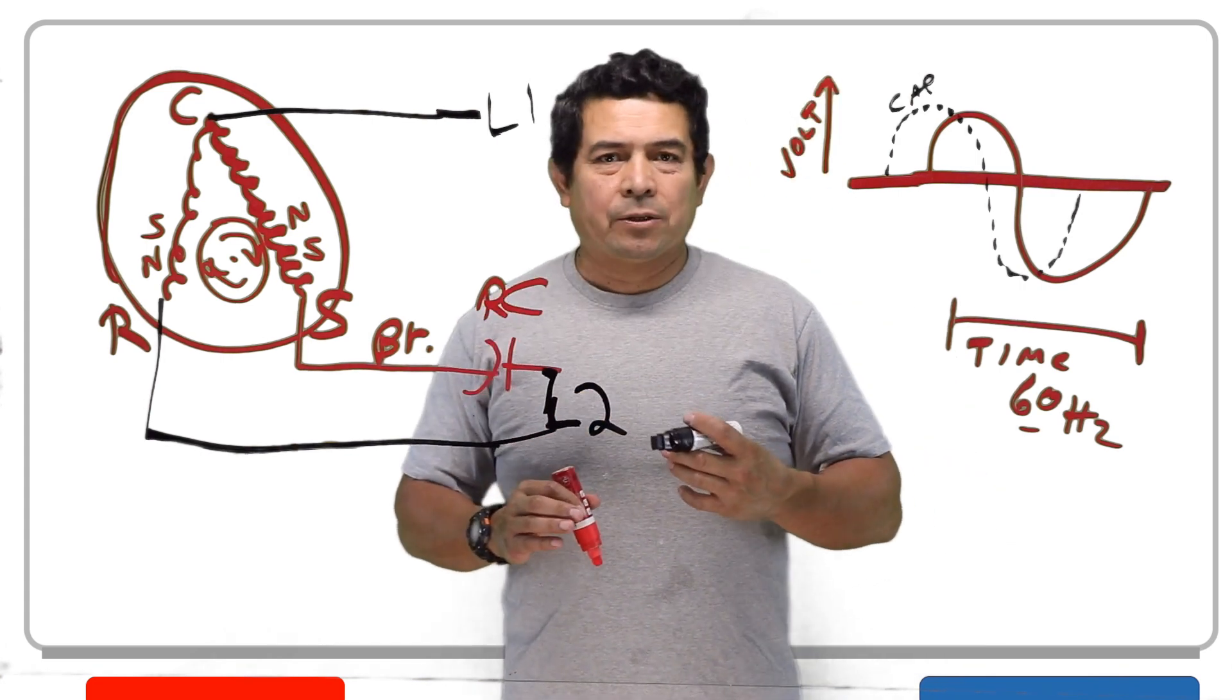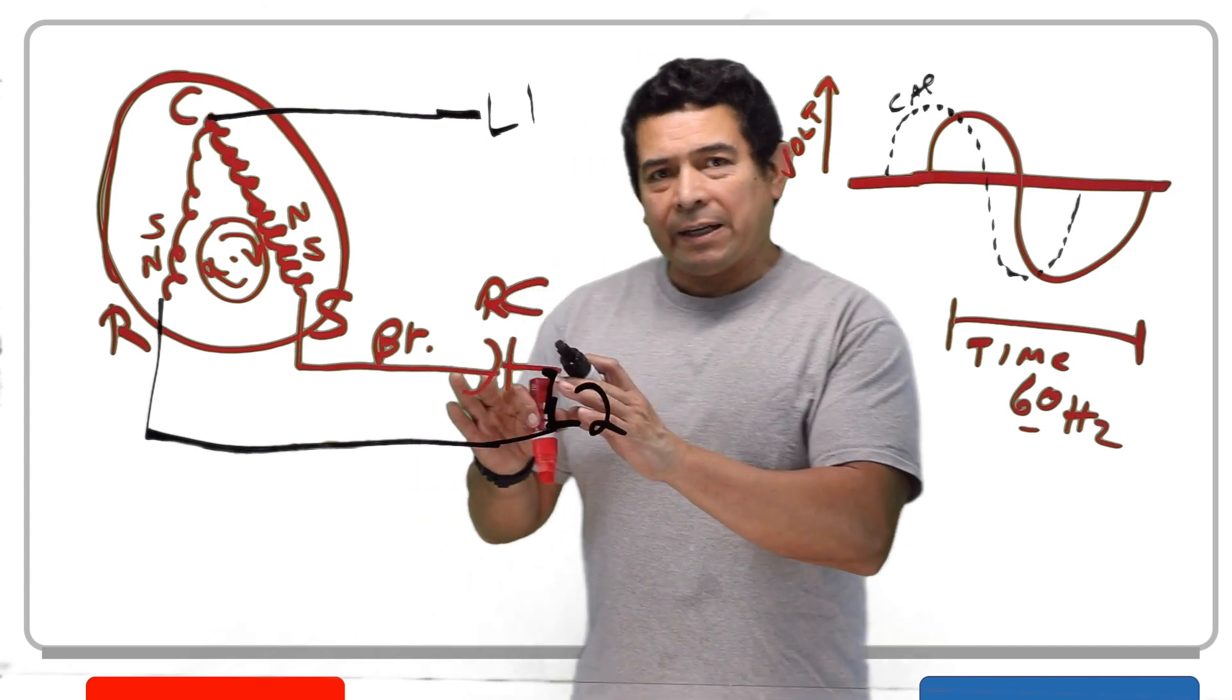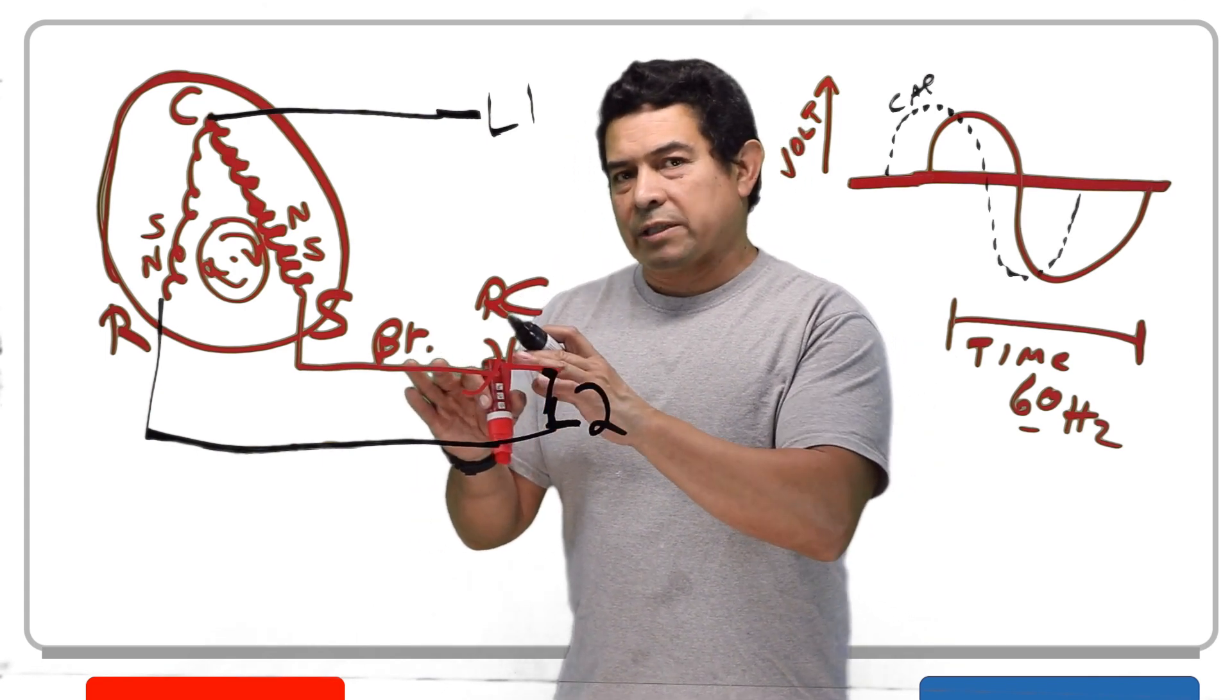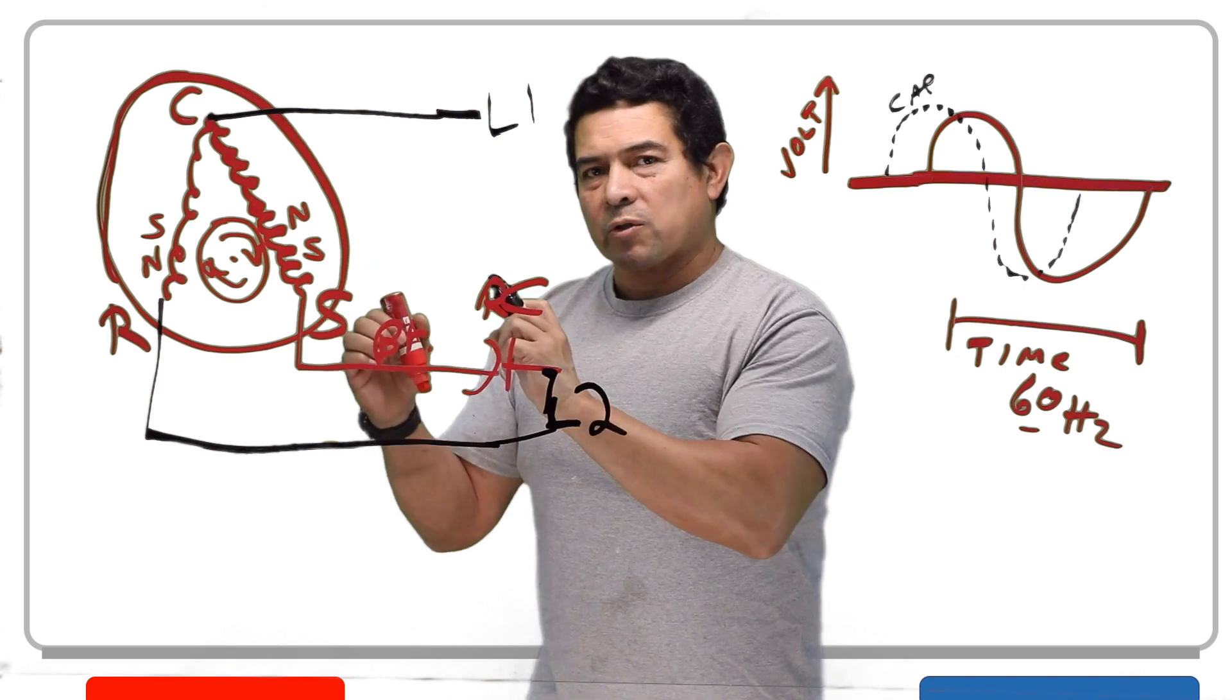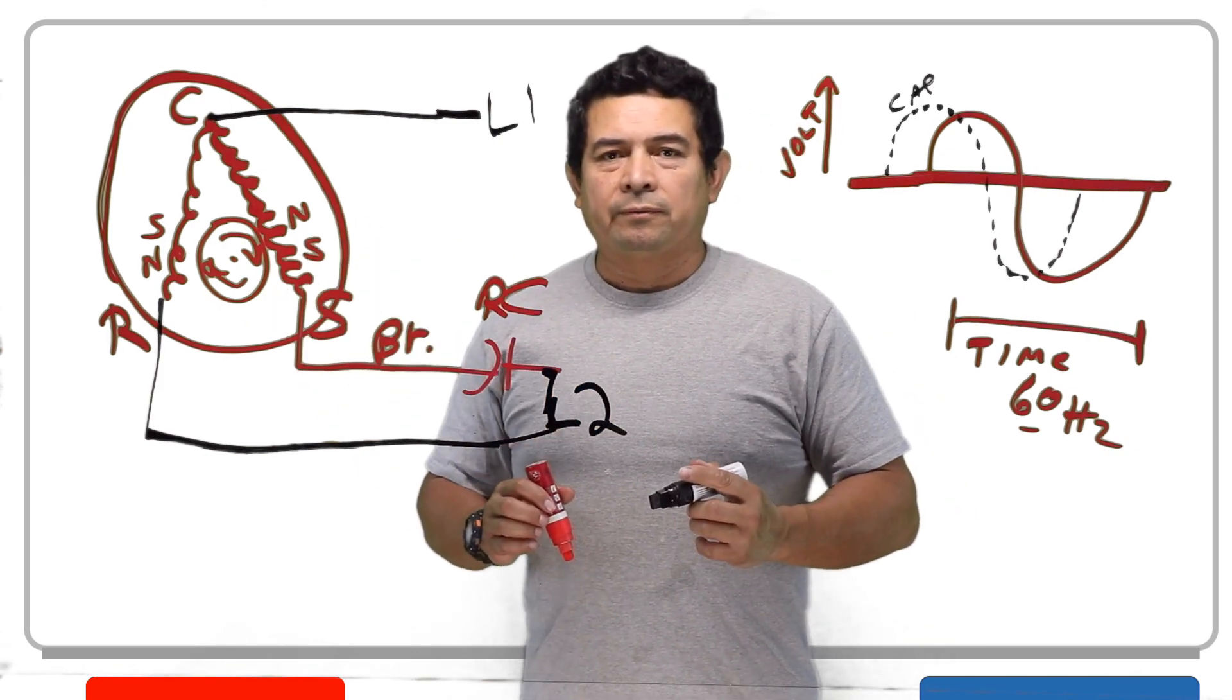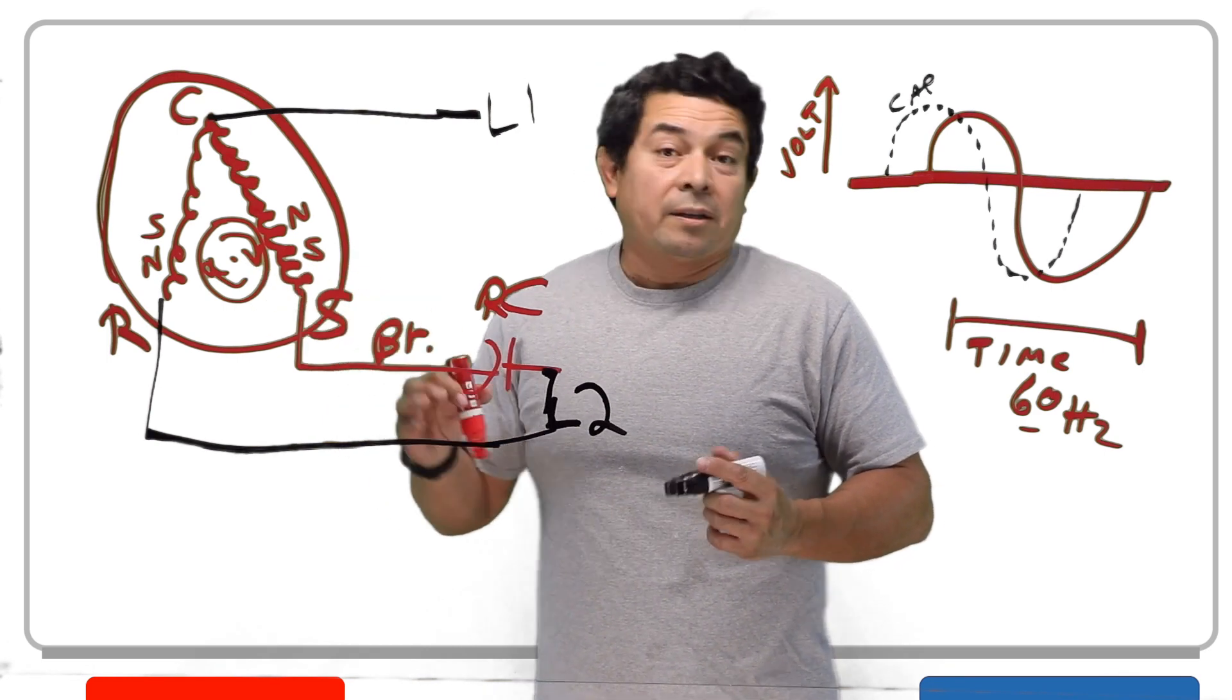So now let's say that your capacitor happens to be bad. If your capacitor is bad and it's not doing anything, what's going to happen now is you can get north on both sides, south on both sides, north on both sides, south on both sides. So that rotor, what is that rotor going to do? It's going to sit there and lock up. It's going to lock up and it's not going to do anything.